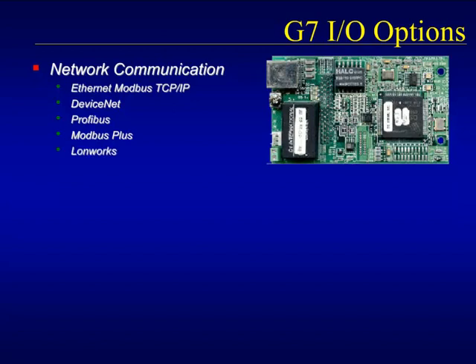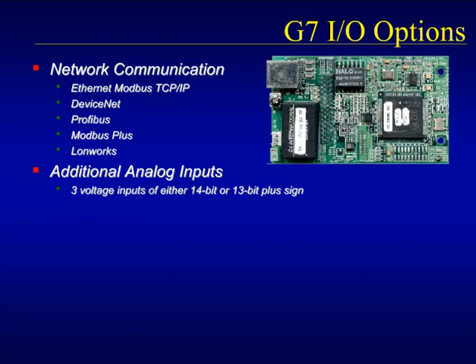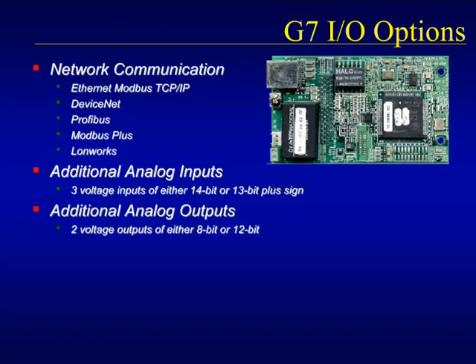Additional I/O includes a high-resolution analog board that will replace the drive's standard analog inputs with high-resolution 14-bit or 13-bit plus sign analog inputs. Using case software and the optional high-resolution board, it is possible to use both the drive's standard analog inputs and the high-resolution analog inputs for a total of 6 analog inputs. An optional analog output card provides 2 0 to 10 volt DC analog outputs as either 8-bit or 12-bit resolution analog outputs to go with the drive's standard analog outputs.